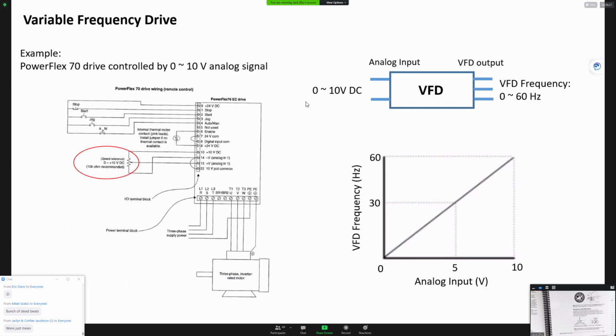For VFD control there are two different ways to control them. One way is directly proportional: you start with 0 volts and 0 hertz, you reach 10 volts, you reach maximum frequency, let's say 60 hertz. Another one is inversely proportional control: you use 0 volts at 60 hertz, and 10 volts at 0 hertz.